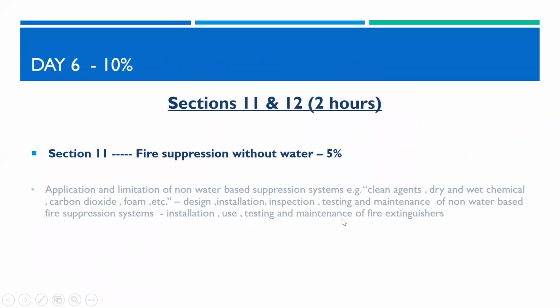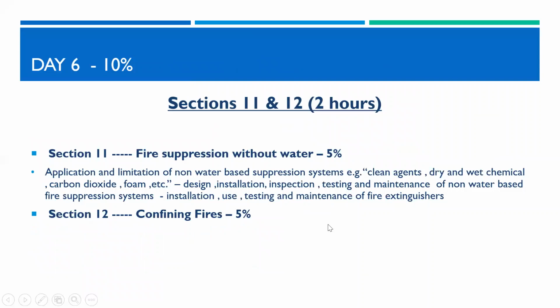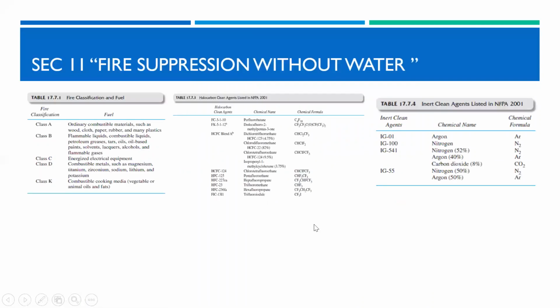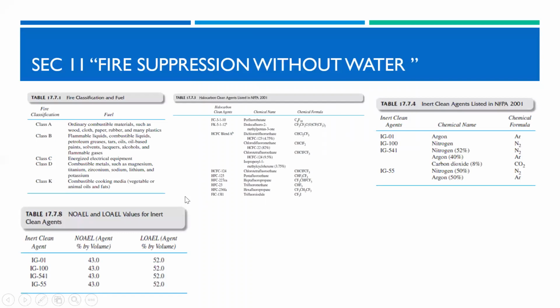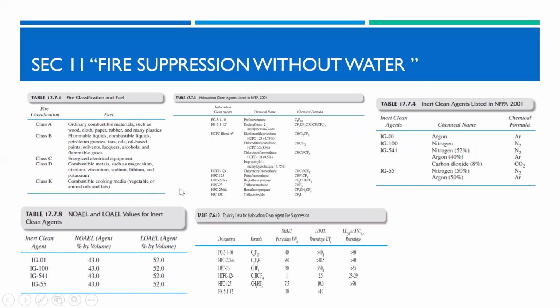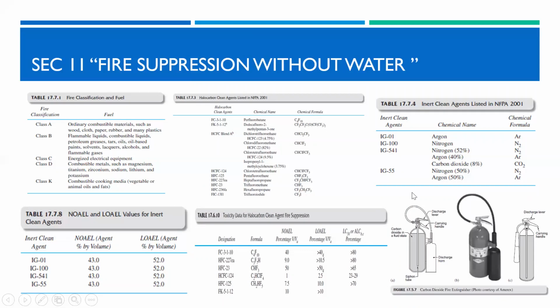Basics of sections 11 and 12: fire suppression without water and confining fires. As we see here, types of fires: class A, B, C, D, K. A, ordinary; B, flammable liquid and combustible liquid; C, electrical equipment fires; D, combustible metals like sodium, zirconium, titanium; K, combustible cooking media like fat or oil. And we use clean agents like halocarbon and inert gas. We have NOAEL and LOAEL. Based on NOAEL and LOAEL, we specify the design concentrations. Under here, we have types of fire extinguishers like carbon dioxide, dry powder, dry chemical, and wet chemical, based on type of fire.